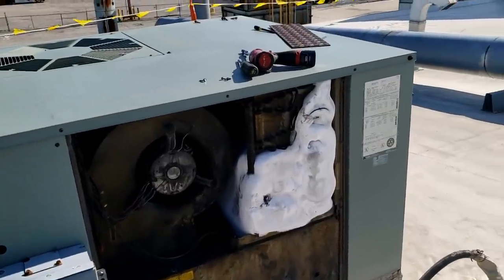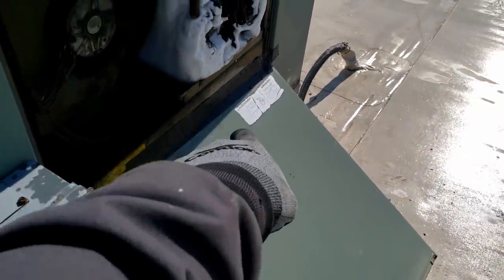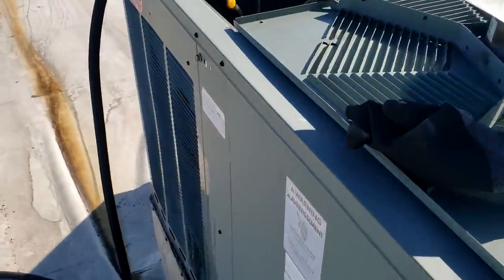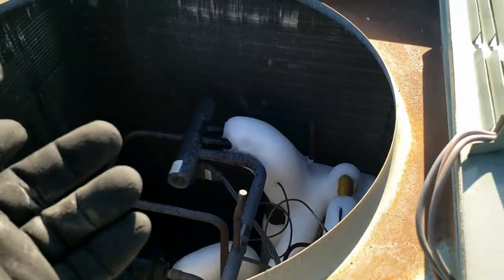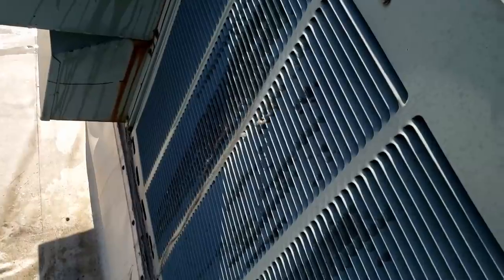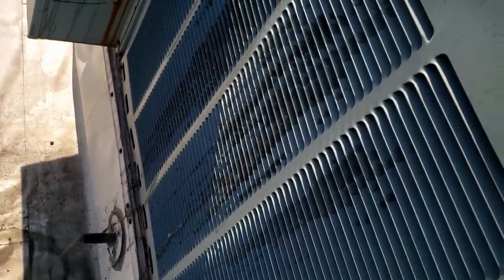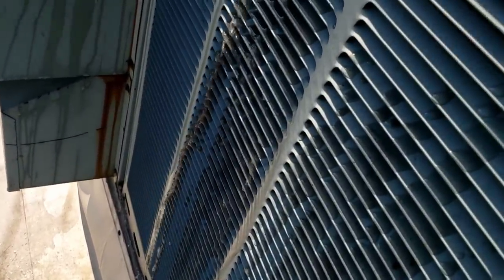This is probably going to make a mess. There were some holes along the bottom — I taped those up and built a little ramp, which isn't really working. So I decided I'm just going to wash this coil out and come back. Then I noticed the reversing valve, so I'm going to force it to heat the coil up to speed things up. Either way we're in good shape because you can see how much nasty crap is coming out of this coil — nice chocolate milk right there.